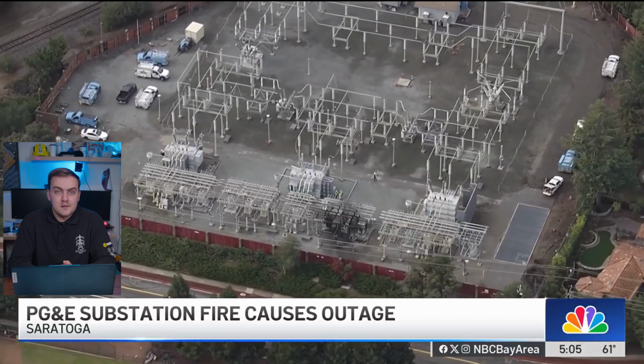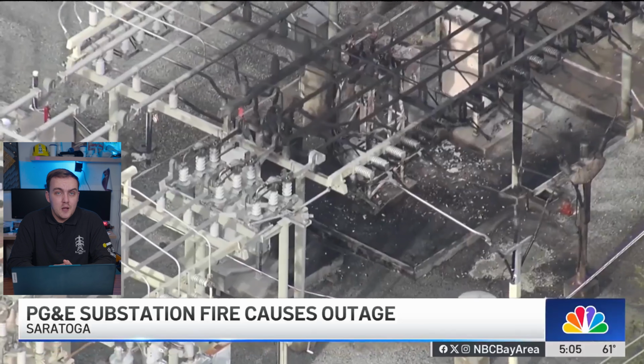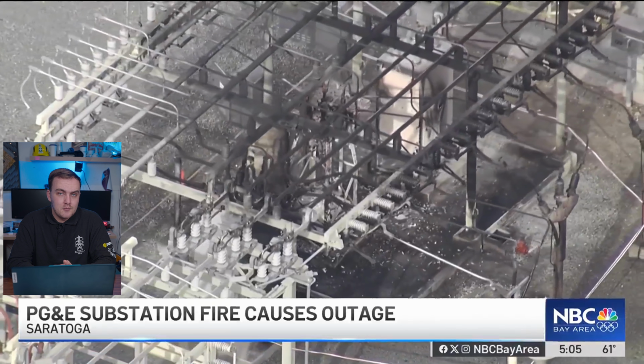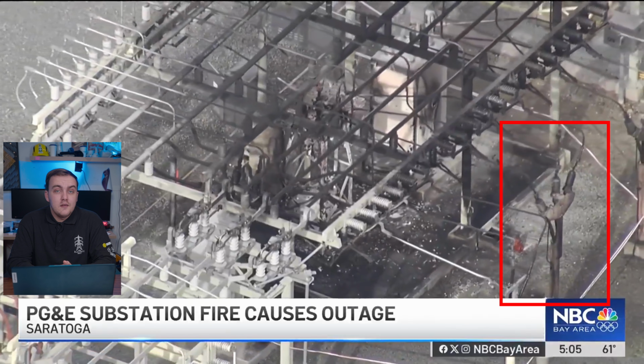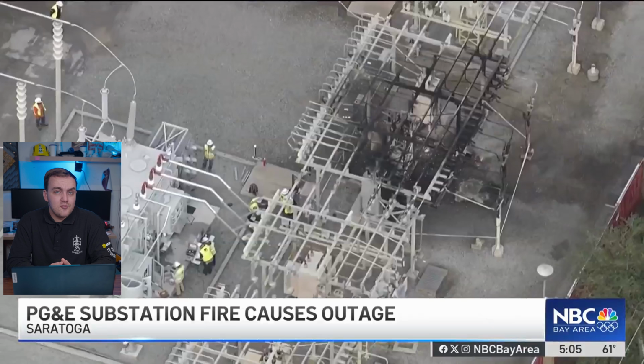Hopefully you learned something new there, but now we need to get to the elephant in the room, or in this case, the big black scorch marks at the bottom of the image. So we covered just about everything on the layout apart from the bits that are relevant to the fire. At the very bottom of the substation here, you can see the bus bars end, and we have this Y shape with three branches going down the structure and into the ground. This is a cable sealing end, and this is where the three-phase bus bars terminate onto a cable, and the cable goes off into the city to power smaller substations, where power is stepped down further to feed homes and businesses. We can see there's a fair few of them fed from this substation, and for each cable circuit, you'll want a circuit breaker to be able to isolate that circuit if there's a fault on it, or just to turn it off for maintenance, for example.